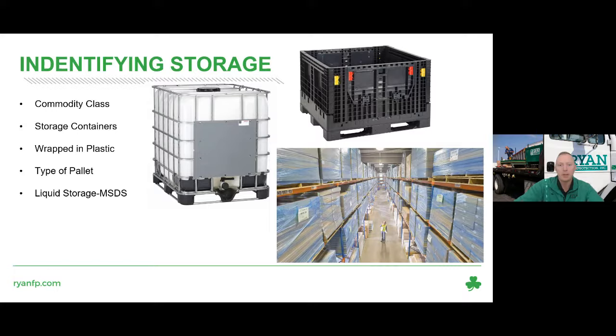Plastic pallets act as fuel to a fire just like a wooden pallet, but the characteristics of plastic don't allow it to absorb water from the sprinkler system once activated. So once a fire starts with a plastic pallet and gets roaring, by the time the sprinkler system operates the plastic is already too hot, and surrounding plastic pallets not on fire can't be pre-wetted to prevent the fire from spreading. The fire keeps spreading, water hits the plastic pallets, bounces off, goes to the floor, and doesn't have the firefighting capability it should.